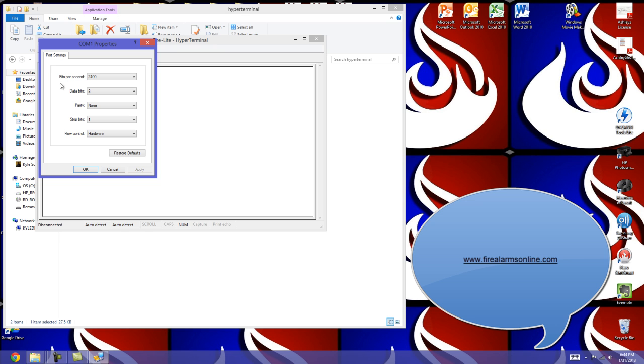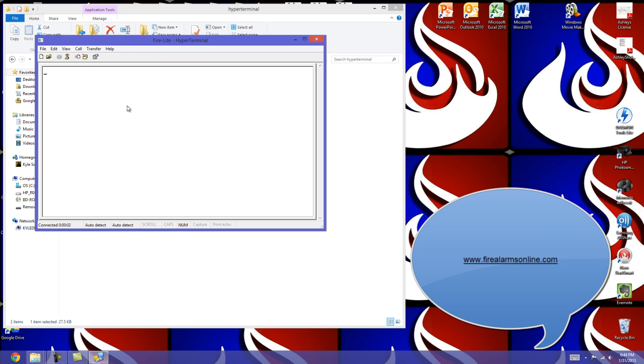And when you get into the port settings, the bits per second for Fire-Lite should be 19,200. Your data bits will be 7. Parity, we'll change it from none to even. Stop bits, leave it at 1. And flow control, change from hardware to none. Tap apply, okay.